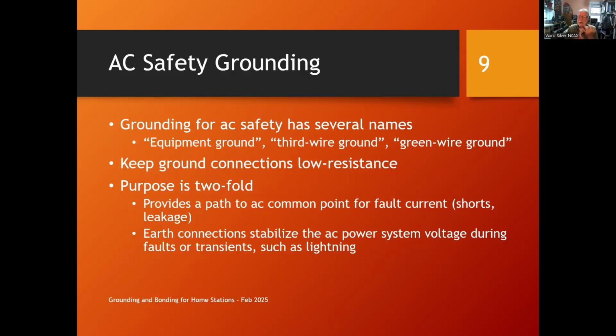And that's to protect you, and it's to protect your equipment, and it's to protect your building to keep a fire from starting. Okay, so low resistance is what you want for AC safety grounding. This only has two purposes. One is it provides a path back to the AC common point for fault current. That includes short circuits and it includes leakage current.